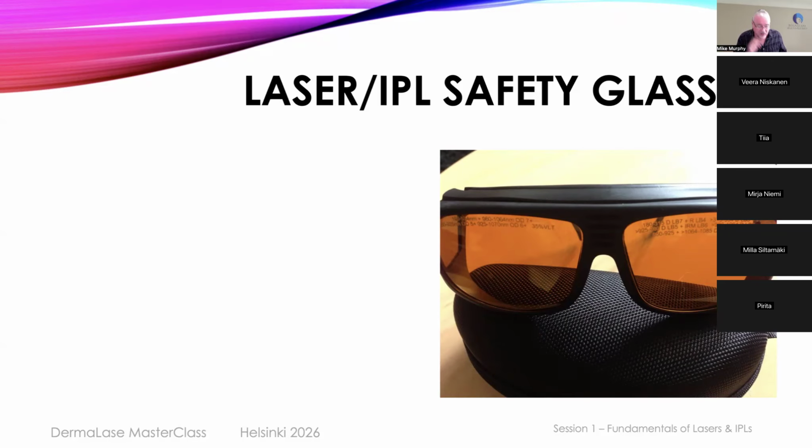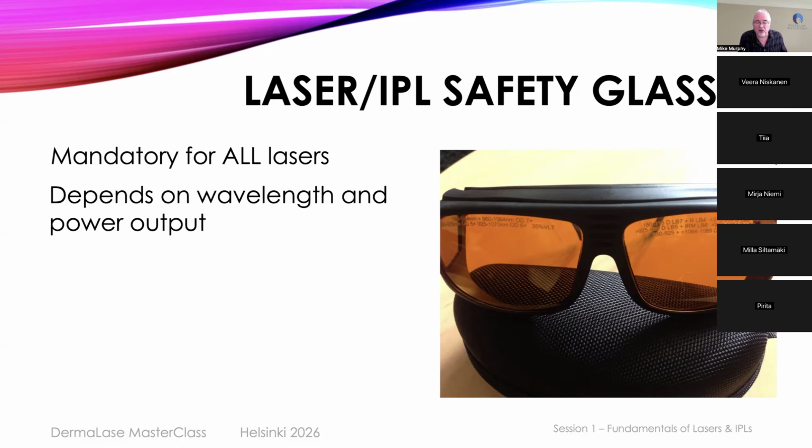Safety glasses are critically important, right? You got to use the right glasses, and people get a bit confused about this. In the EU, it is absolutely mandatory that you wear the correct glasses for whichever laser you're looking at. The glasses safety factor depends on the wavelength and the power output of your laser. So the glasses have to be aligned with both wavelength and power of your machines.